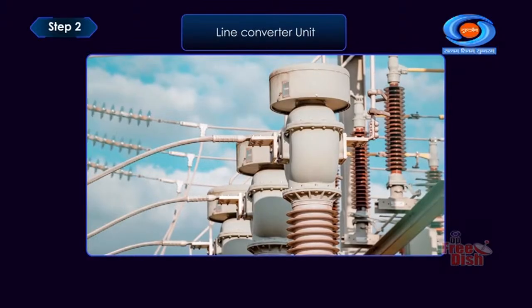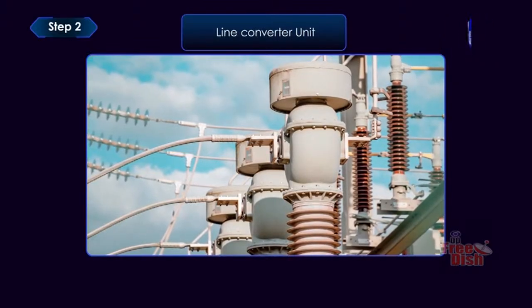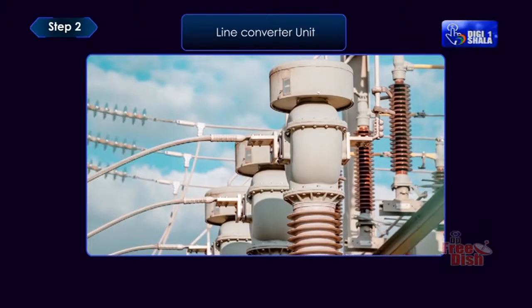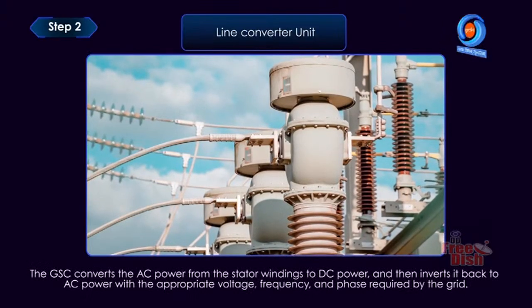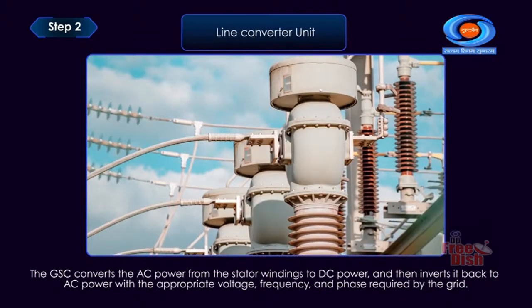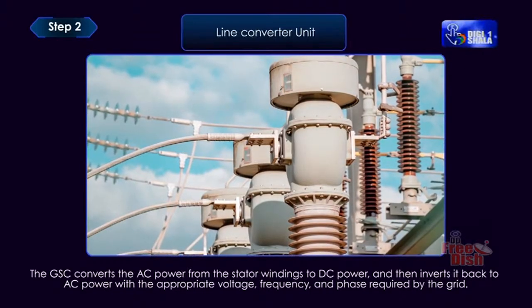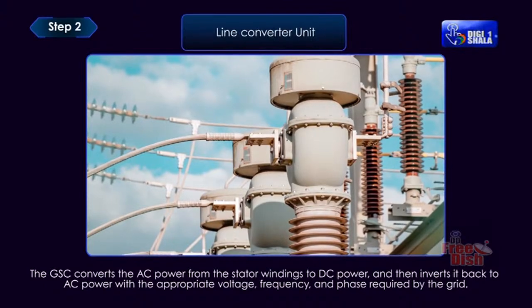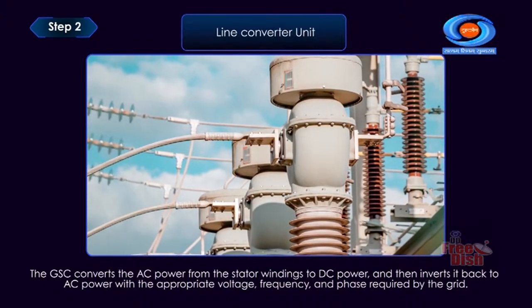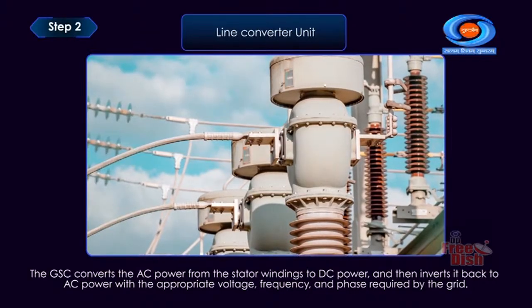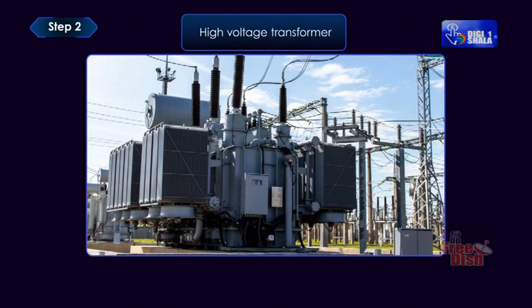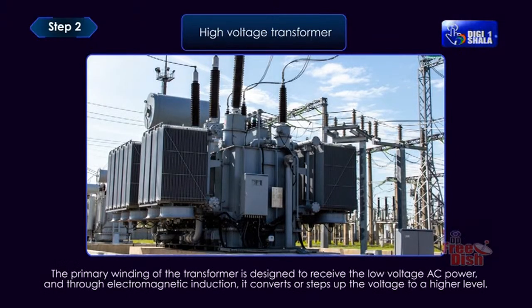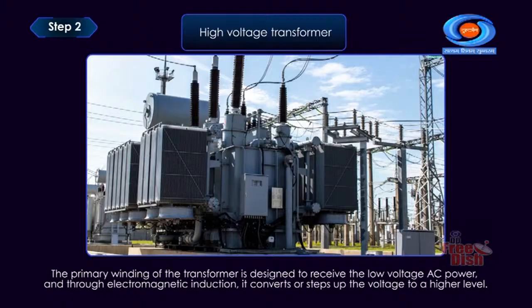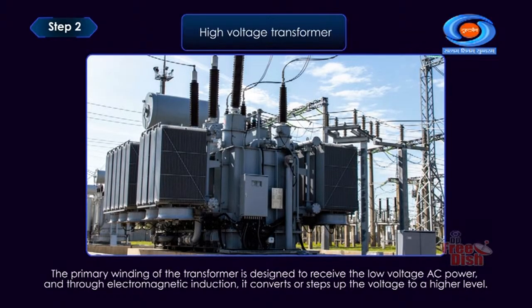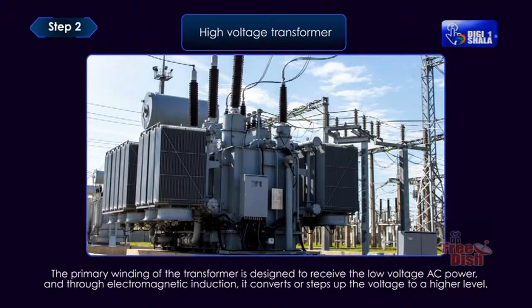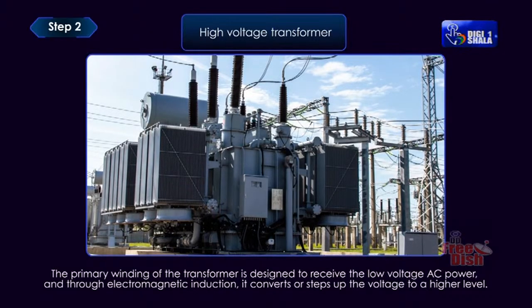Line Converter Unit. The LCU also includes a grid-side converter (GSC) connected to the stator windings. The GSC converts the AC power from the stator windings to DC power and then inverts it back to AC power with the appropriate voltage, frequency and phase required by the grid. High voltage transformer. The primary winding of the transformer is designed to receive the low voltage AC power and through electromagnetic induction, it converts or steps up the voltage to a higher level.